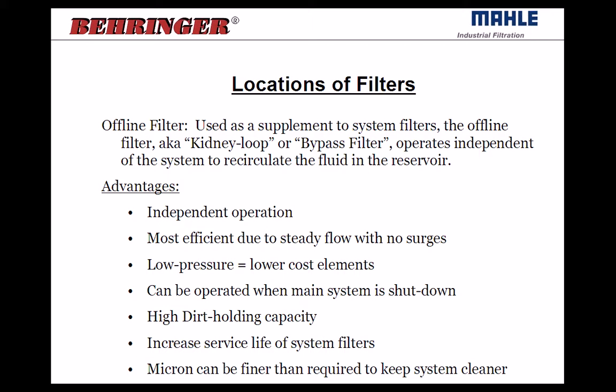And it has a lot of advantages, some of which are independent operation. It has, like I said, a built-in pump motor combination, so it doesn't operate off of the system pressure. It can be run even when the system is shut down, or totally independent of the system. It's the most efficient form of filtration because it's a constant, steady flow, with no flow surges and no pressure spikes, nothing associated with cylinders going in and out and different flow rates. The filter and housing are low pressure, so it has lower cost elements. Again, it can be operated when the main system is shut down, so you can continuously filter the oil in the reservoir.